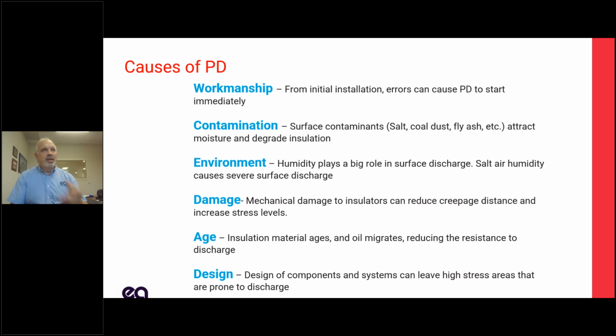We clean insulators because they get dust on them. Well, dust isn't necessarily all that conductive, but once I start adding humidity to it, and then dust will trap and hold humidity, that gives us a point for discharge. The environment, like I say, humidity, however it exists, whether it's airborne humidity or it's collected in dust on the surface, can be a big contributor to surface discharge. Salt air is even worse. I don't know if I've got any island utilities or customers that live right by the ocean. Salt air is a big problem. It causes a lot of surface discharge because salt air humidity is conductive.